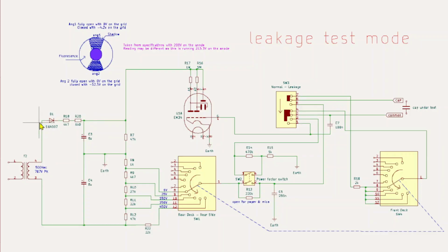The old circuit had a selenium rectifier here with 26 or 25 separate elements, and each element is said to drop 1 volt. So we're expecting about 25 or 26 volts across there. Let's err on the side of caution and say we have 26 volts across that stack. Now, what does that leave us with? Well, that leaves us with 681 volts across those two capacitors there. 707 volts minus 26, so 681 volts.